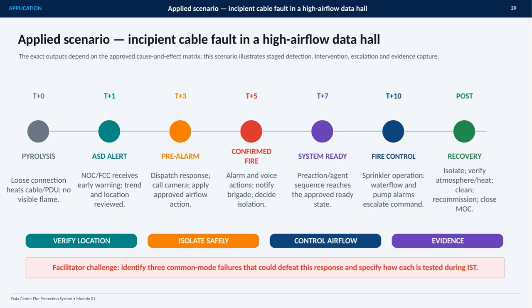The sequence then moves towards system ready, fire control through sprinkler operation, and escalating water flow and pump alarms, and finally recovery. Recovery includes safe isolation, atmosphere and heat verification, cleaning, recommissioning, and closing the management of change process. Throughout, the team should verify location, isolate safely, control airflow, and preserve evidence. The facilitator challenge is to identify 3 common mode failures and explain how each will be tested during integrated systems testing.